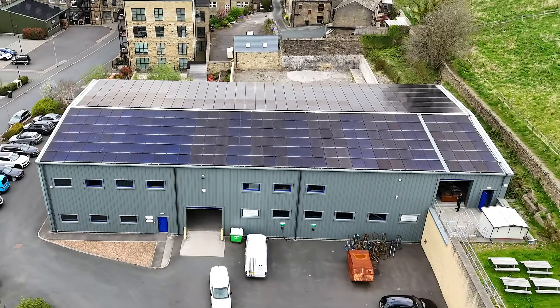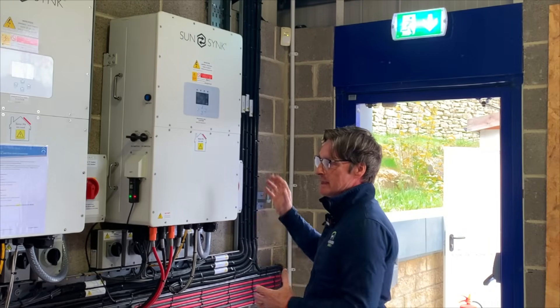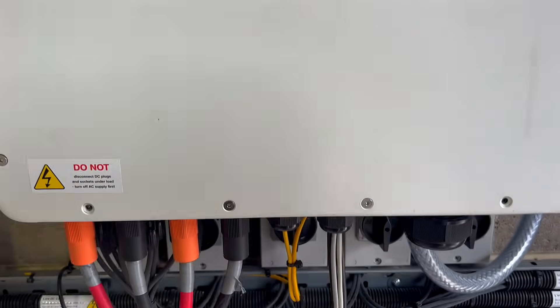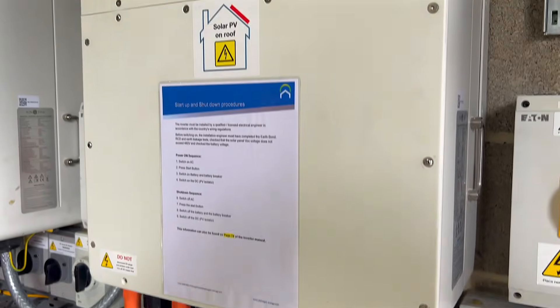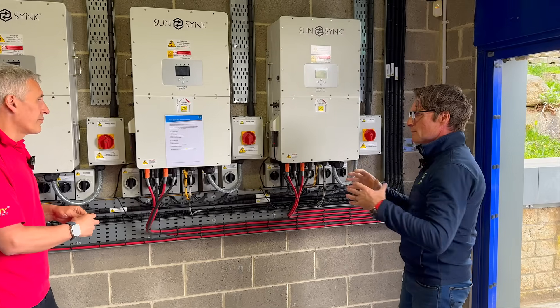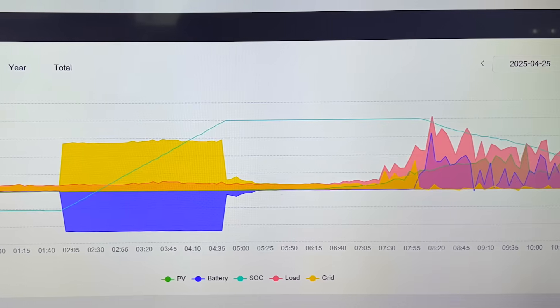How does that integrate with the Sunsynk hybrid inverters? You take one 50 kilowatt inverter and dedicate it as the master inverter. Then you create Modbus 1 and Modbus 2, which become the slave inverters. The master inverter reads what everything else is doing, and that information is sent to the Connect app, which gives you an overall reading of what's being produced.